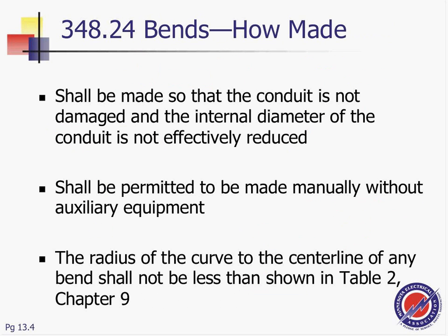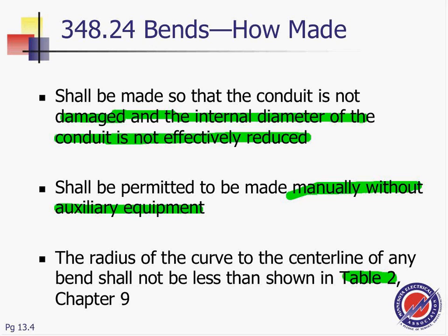Bends: How Made. Shall be made so that the conduit is not damaged when you bend it? The diameter of the conduit is not effectively reduced. Would you use a Chicago bender or a hydraulic one? No, manually, without any auxiliary equipment. Bends shall be permitted to be made manually. You don't need a hydraulic bender to bend a flex. The radius of the curve from the center of any bend shall not be less than that shown for other bends in Table 2, Chapter 9.